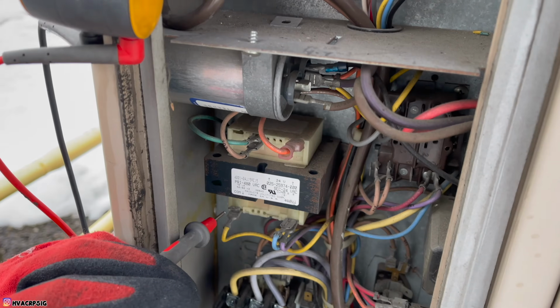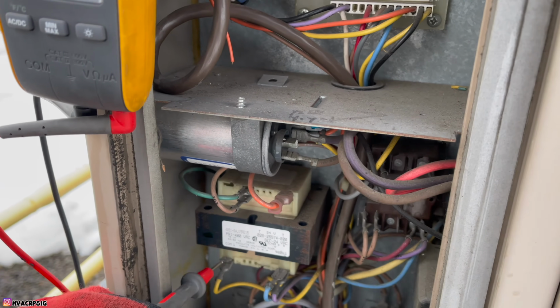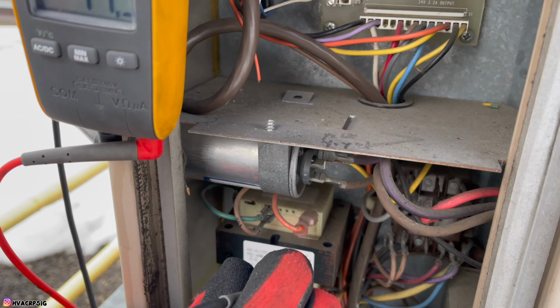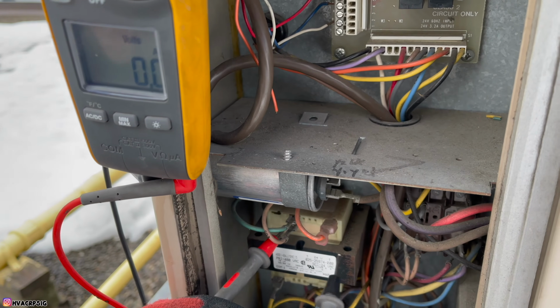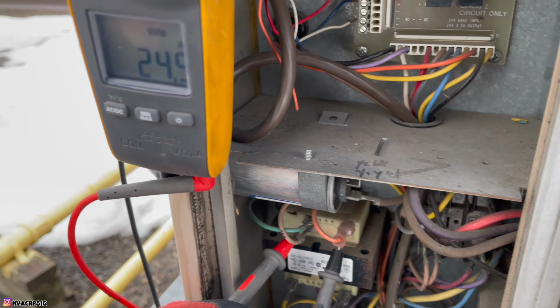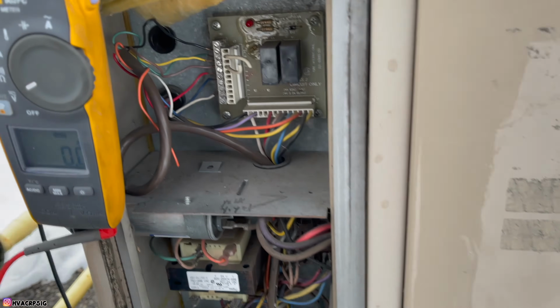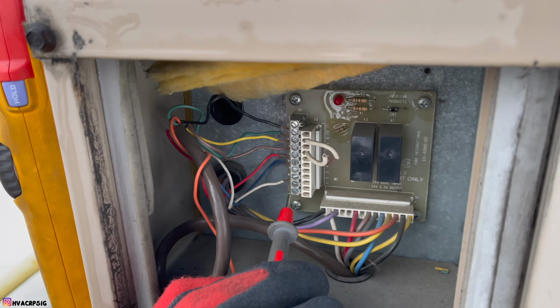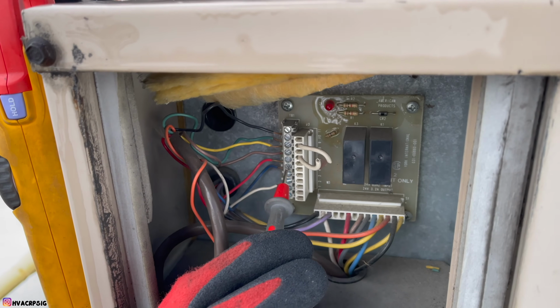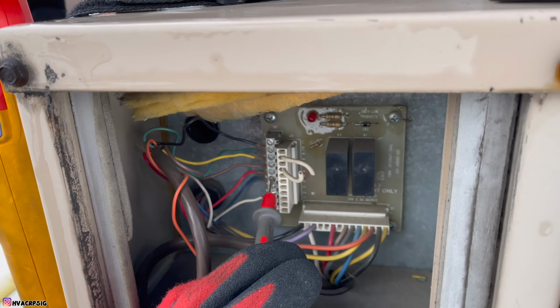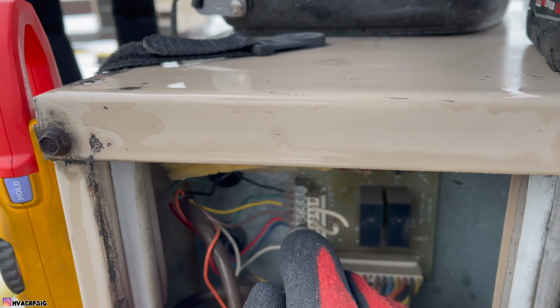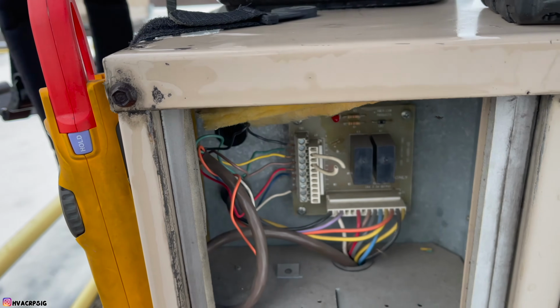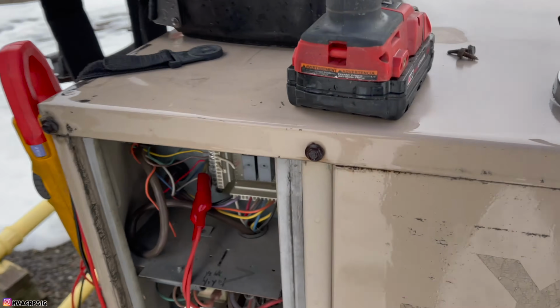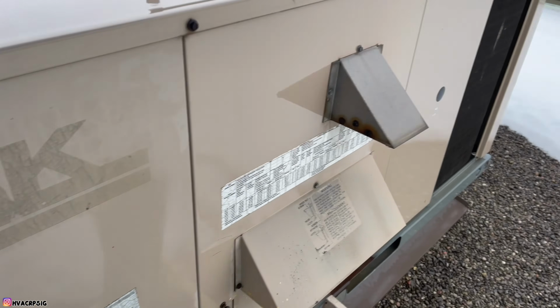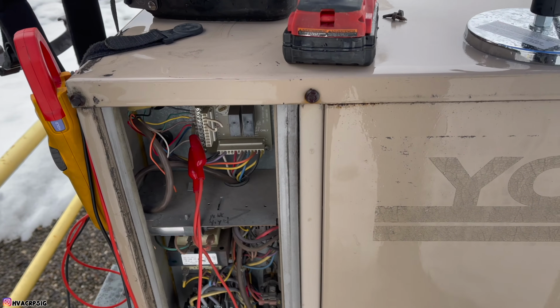So now we're gonna check to make sure that other transformer is actually giving us our control transformer 480. 447 should be good enough. Now we should have 24. Let me check this. Okay, we do. So we got 24. Now what we're gonna do is check our actual terminal block here. So nothing's calling. Let's check R here. And this brown here is the C. Okay, we have 24. So what is the call? So what he did here is he's jumping out the thermostat, taking it out. Eliminate that, or we can narrow it down to that possibly being the issue.